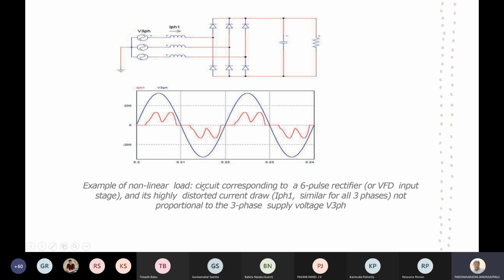This diagram will give us a clear understanding of the nonlinear load concept. These loads are connected at the point of common coupling. Here, taking this load, this is a rectifier. Whenever it is activated by the 6 pulse circuit, this 6 pulse rectifier draws a highly distorted current. Here the actual supply voltage is V phase, this one, whereas the output keeps changing like this. IPH1 refers to the highly distorted current, not proportional to the three phase supply voltage. The red color is the output current.